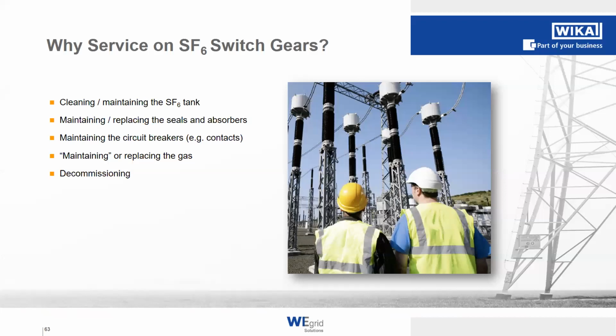When I talked about the GAD before, we were really focusing on the humidity aspect within the gas. But still, there is the absolute need from time to time to clean the gas compartments, to clean the SF6 tank. You have to, at one point, definitely go into the compartment and change the seals and the absorber materials. Well, you can prolong all those time intervals with the GAD, but in the end, there are certain times where you have to use a different gas handling unit.